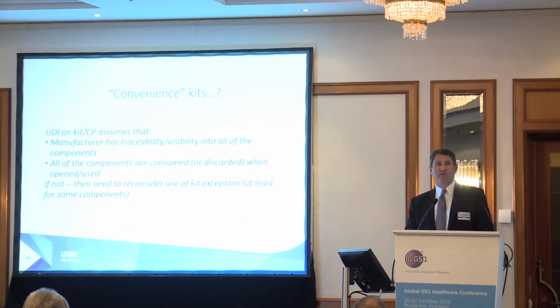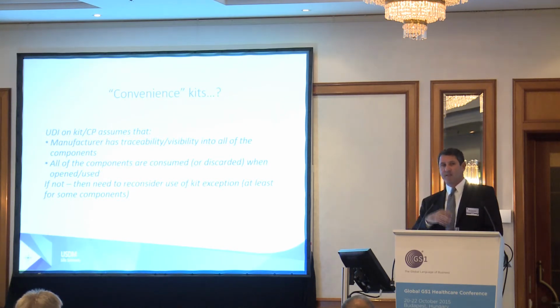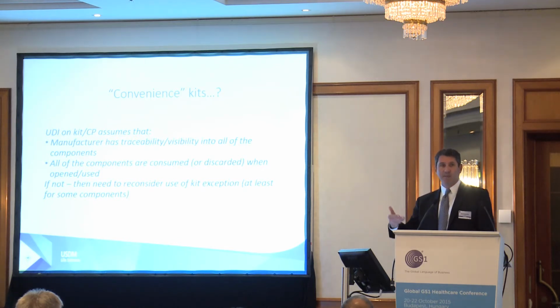The other one, which creates quite a bit of confusion in the US, is the idea of a kit exception. In the US we have this exception that says if I put a UDI on the kit, the convenience kit combination product, I don't need to put a UDI on the individual components. What we didn't say explicitly in the rule, and in retrospect I wish we did, was that this assumes that the kit stays together over the life of that product. So understand the foundation, the mental model of this exception, and depending on how this plays out in Europe, I would encourage you to be very explicit about when the exception is appropriate and when it's not.